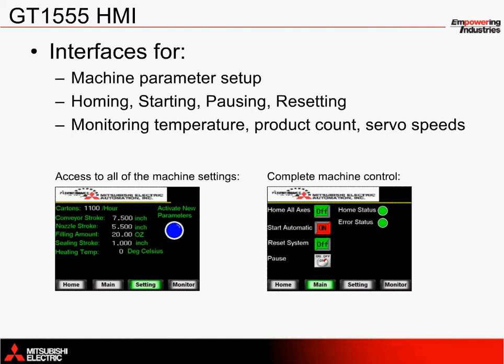The GT1555 graphic operation terminal complements the filling application with easy-to-configure user screens for operator control. The screen on the left illustrates how an operator can interact directly with the machine during initial setup. These settings are directly written to a structured text PLC program to initialize or reinitialize variables such as the cartons per hour, cam stroke amounts, the heating temperature, etc. A screen is also included to start and stop the machine's operation, reset the system, perform homing, and to monitor for errors.